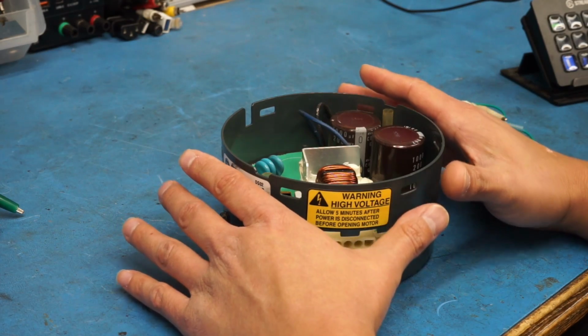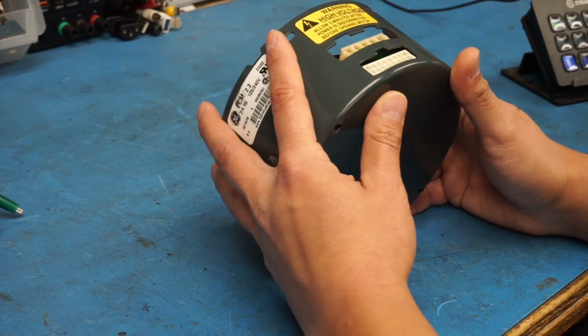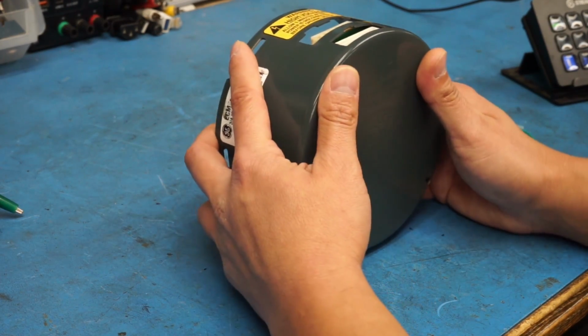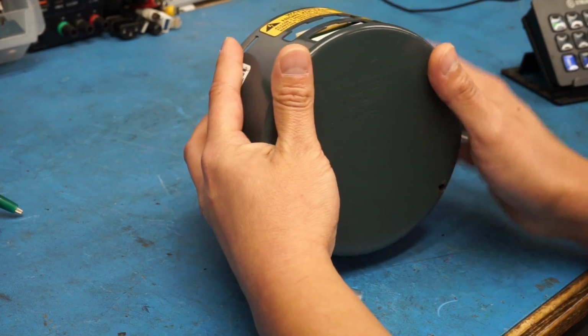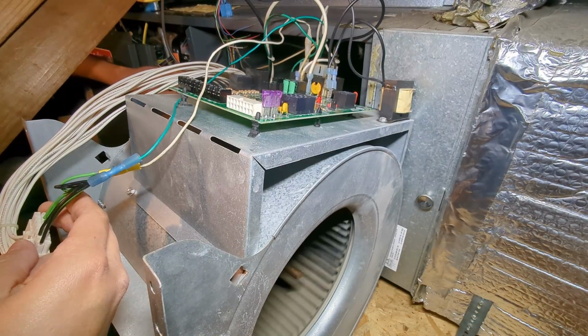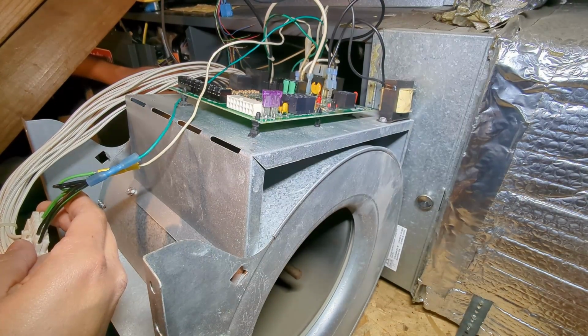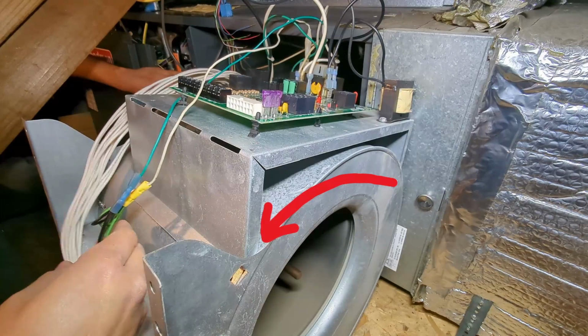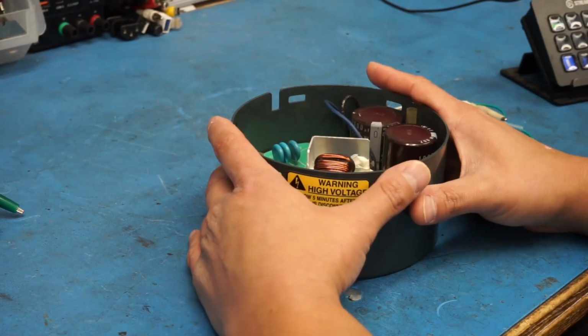I didn't realize that LE stood for lead end, which basically means that's the direction you'd see the motor rotating if you look at it from the end where the leads and wires come out. I installed the controller on the motor, applied power to the test leads, and the motor rotated backwards, or counterclockwise. If I had bought one sold as counterclockwise LE, I would have been fine.